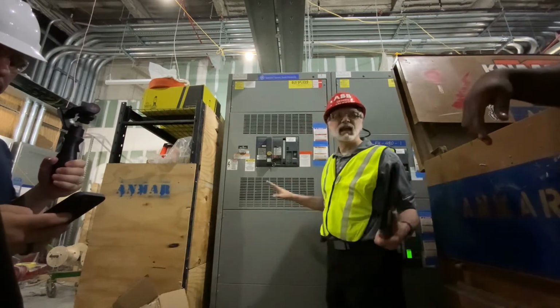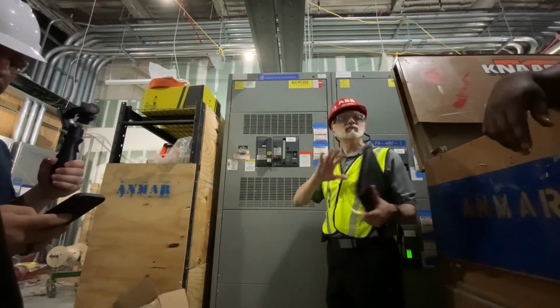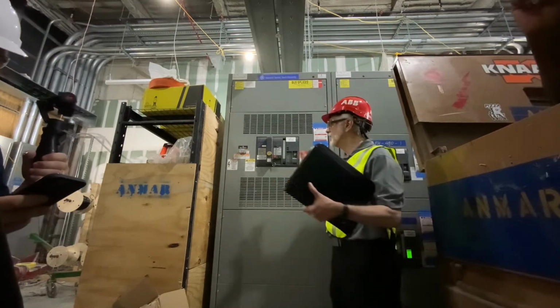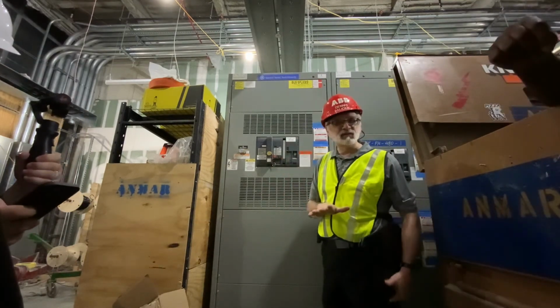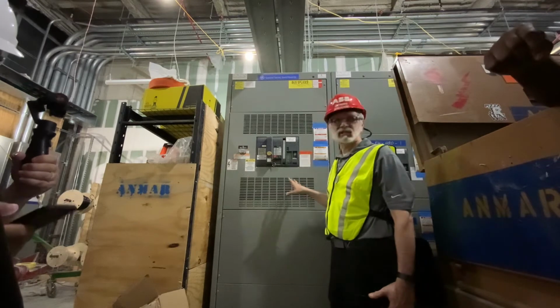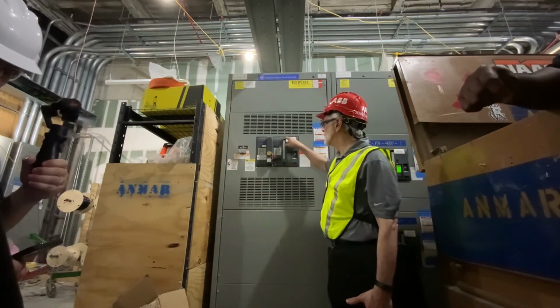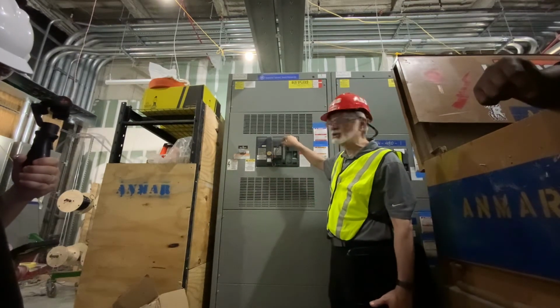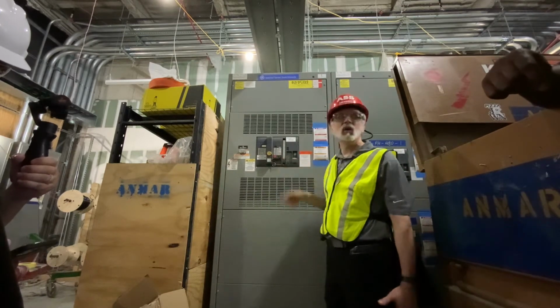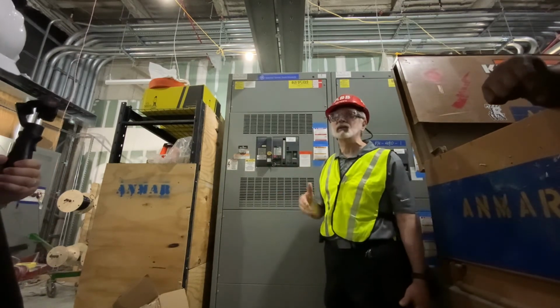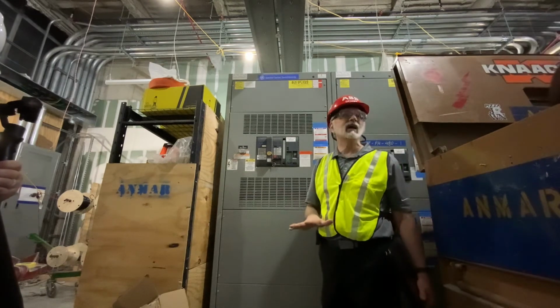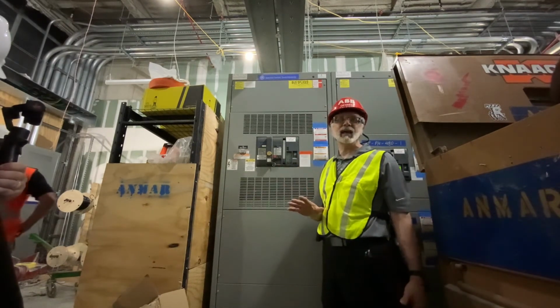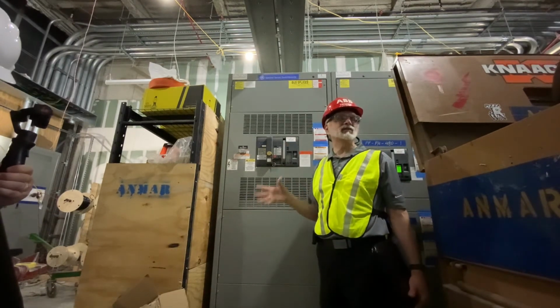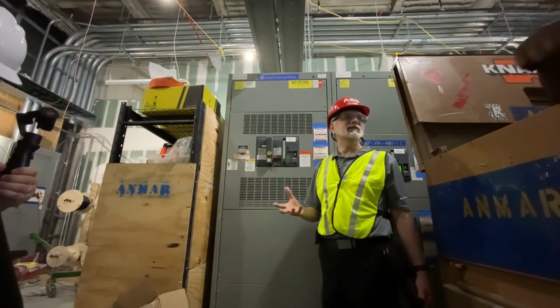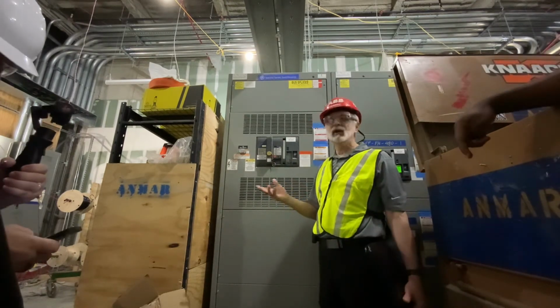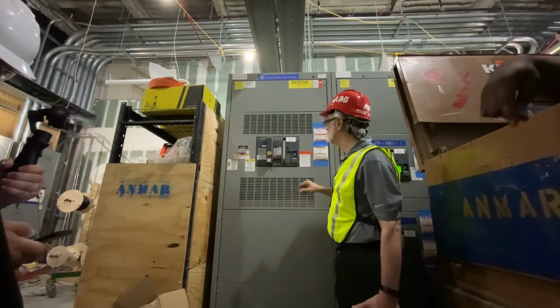From a maintenance standpoint on the switchboard, just like all the other pieces of equipment, keep it clean, use vacuuming, and exercise the breakers. We've already talked about how to charge. Just work it through once a year. Breakers do not like to be left idle. The one thing you don't want to have happen is the breaker calls for a trip and it hasn't been exercised, and we have an issue. So we're trying to avoid that.